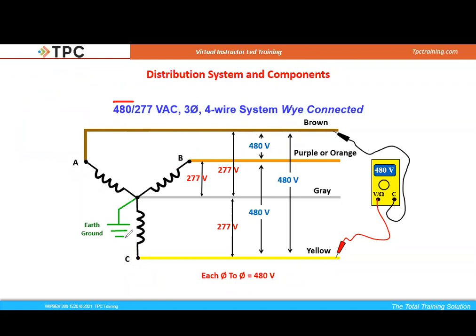When we establish our connection to ground, which we're going to do through a grounding electrode conductor connected to some grounding electrodes, usually a metal water pipe, building steel, the rebar in the concrete, or even something a little bit more familiar, maybe ground rods. When we do that, we establish what we call a neutral. And so we're actually going to be bringing four wires into the facility, three energized conductors and a neutral, and the neutral is connected to our grounding electrode system.